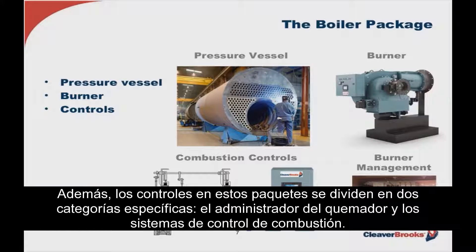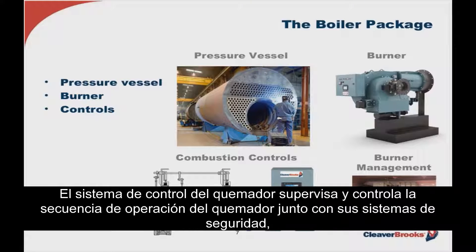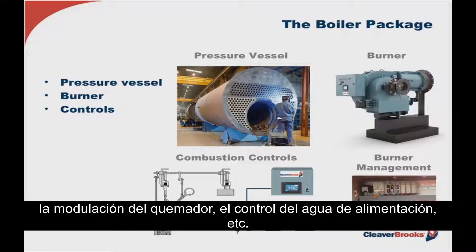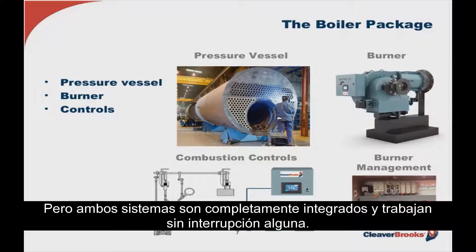The controls on these packages are broken down into two specific categories: the burner management and the combustion control systems. The burner management control system supervises and controls the burner sequence of operation along with its safeties, while the combustion control system manages and controls the fuel-air settings, burner modulation, feed water control, draft control if applied, and so on. Both systems are fully integrated and work seamlessly together.